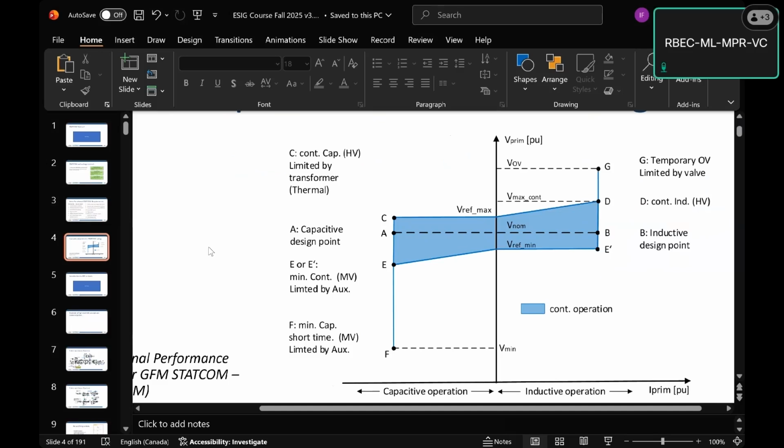Yeah, and I'm not going to spend a lot of time on it now, but you're touching on a few really important points. So one is that a STATCOM is just another tool in a toolbox, and actually for many years, while GE held a patent on voltage control for wind farms, which was one of the most insane patents I've ever seen, Vestas had to install a bunch of little STATCOMs alongside their very capable voltage source converters. They had wind turbines that could do this. They had the same capability, but they were constrained by patents. They couldn't do it. So they built STATCOMs alongside their plants, and those went into service all over the place.